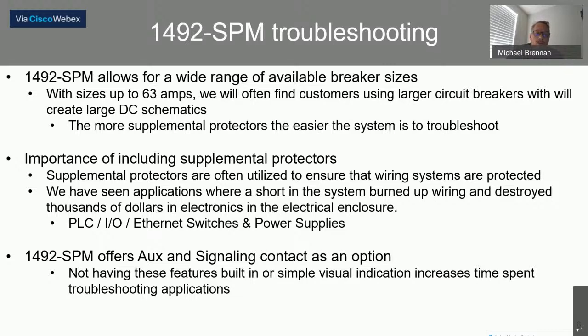One of the things to remember is branch circuit protection is required, but supplemental protection is often utilized to protect the wire gauge that's below it. So it's very important that we include supplemental protectors. We have seen applications where customers have forgotten supplemental protectors, and they had a short in one of their end devices, and it actually burned up some wire, specifically in a conduit, and ended up destroying thousands of dollars in electronics in an enclosure. So they lost the PLC, they lost I/O, Ethernet switches, and power supplies. So it's very important that we make sure that supplemental protectors are included.